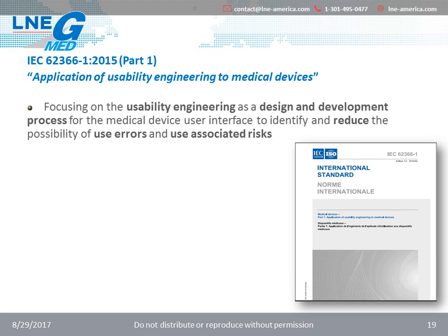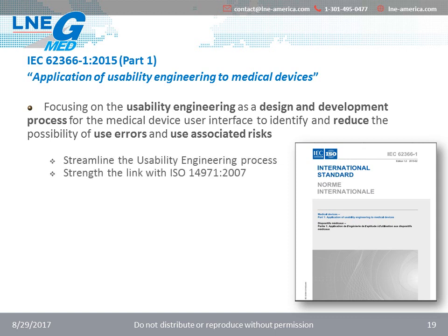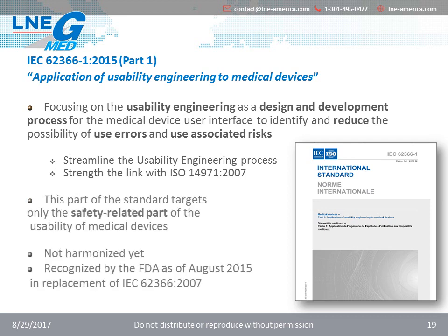This version is focusing on the usability engineering as a design and development process for the medical device user interface to identify and reduce the possibility of use errors and use-associated risks. This version streamlines the usability engineering process and has closer ties to risk management. This part of the standards targets only the safety-related part of the usability of medical devices.